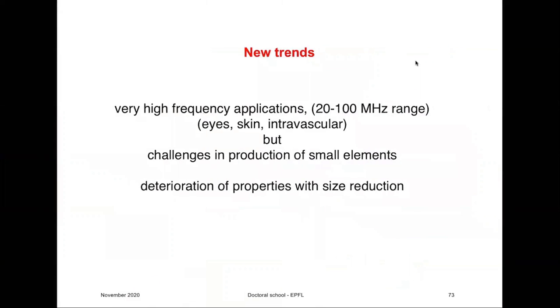Now the new trend in imaging is to go to very high frequency applications. We are talking about the 100 megahertz range, where you can see sub-millimeter objects, for example for skin cancer, for ophthalmology, and so on. There are challenges in producing small elements, and there is always deterioration of properties with size reduction, because you have to do a lot of machining, and that can induce defects. People manage to do this, but it's difficult, expensive, and few companies are able to do that.